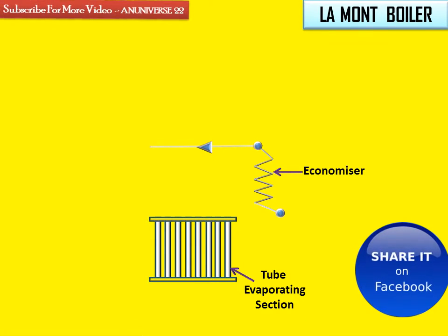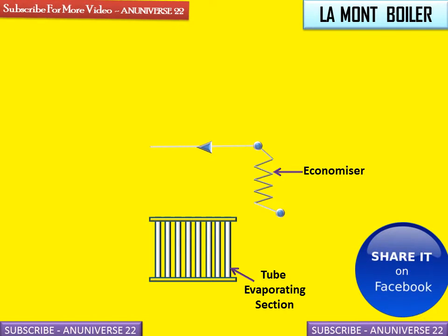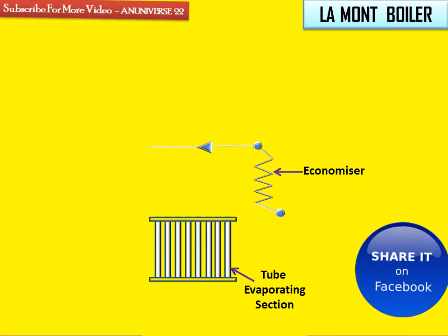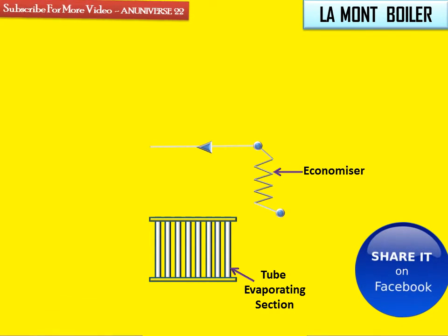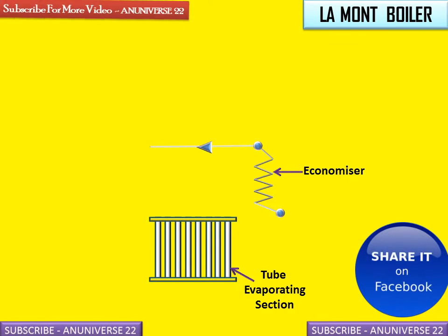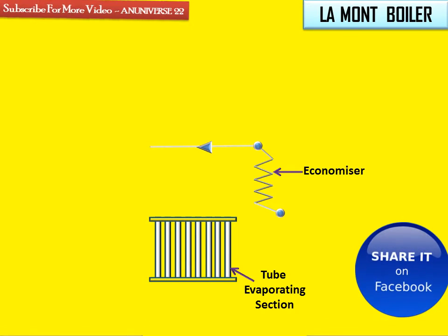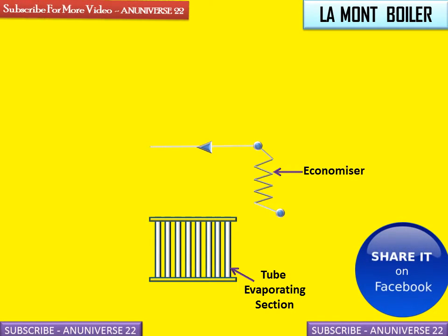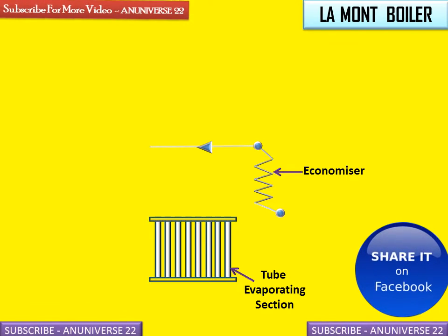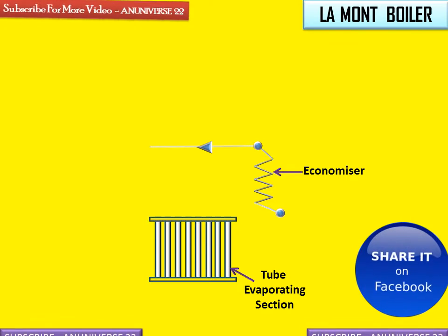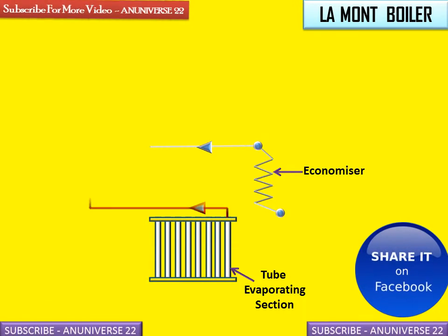This is the economizer. The economizer is used to preheat the water by using the remaining heat of the combustion flue gases, and it increases the boiler efficiency. The feed water is first supplied to the economizer before entering the boiler.